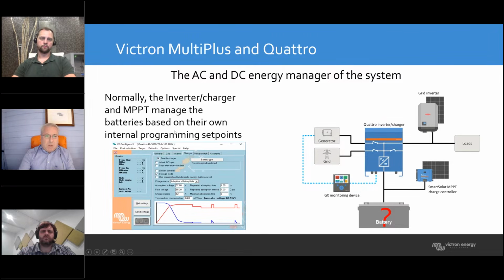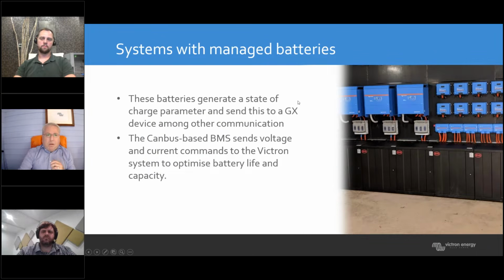One of the things that's come along with some of our software, particularly our GX devices like the Cerbo GX or Color Control GX, is that we're now able to listen to battery manufacturers' BMSs directly using CAN bus communication. So it's able to take commands directly from the BMS of the batteries, and that BMS controls the charge parameters of the inverter charger, and with our systems, also your solar charging when using the MPPTs on the DC coupled side of things.